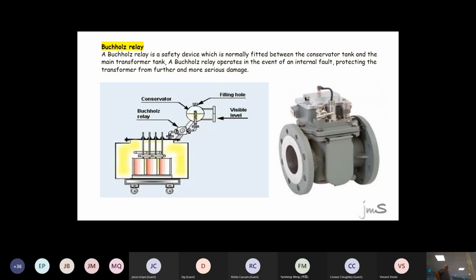So, what's the purpose of the Buchholz relay? Is it there for overload current? Is it for short circuit current? Is it there to detect any type of moisture or maybe bubbles, not moisture, bubbles inside the oil? That's the one. You guys with me? And they asked that in the exam. So, this Buchholz relay, you can imagine the oil flows through it. And as the oil flows, air will go up and it will activate the switch inside.